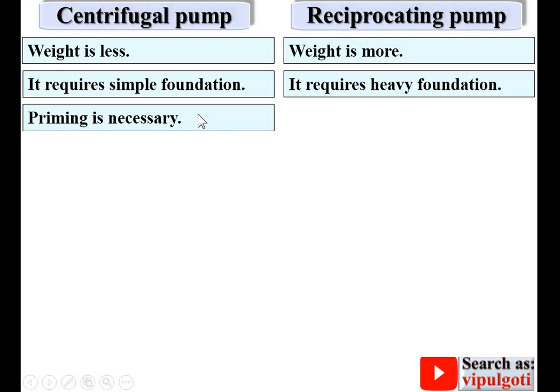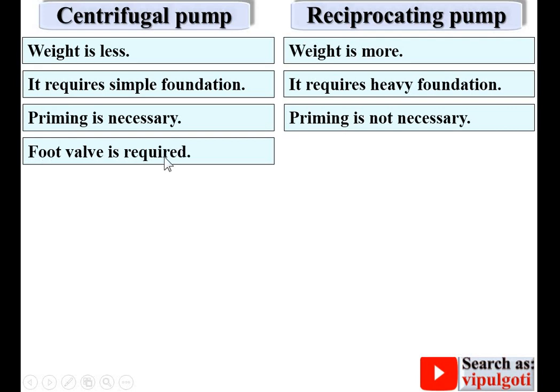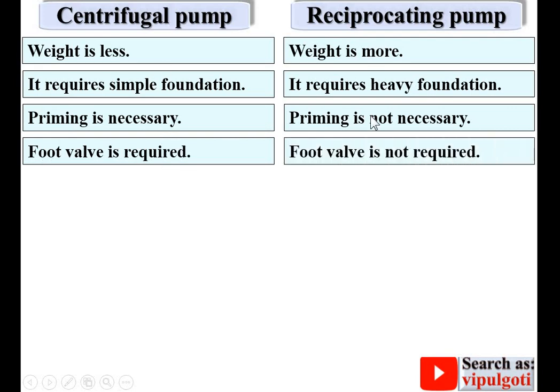Priming is necessary in case of centrifugal pump, whereas priming is not necessary for reciprocating pump. A foot valve is required in case of centrifugal pump, while a foot valve is not required for reciprocating pump.